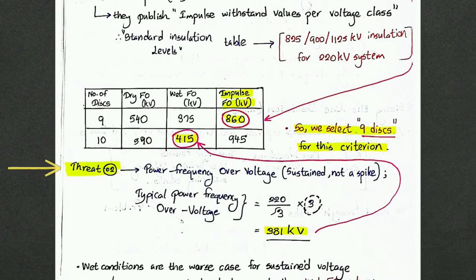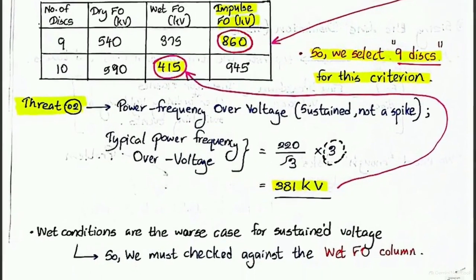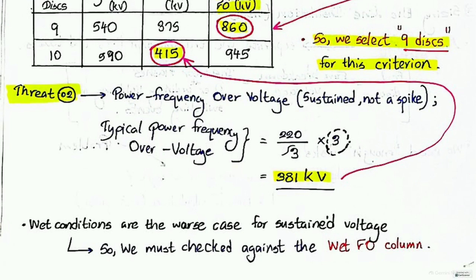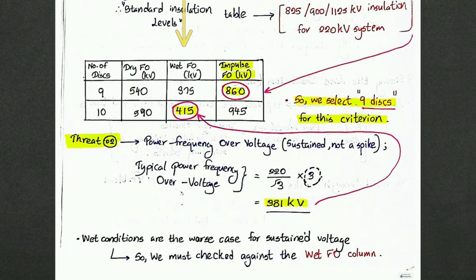But we also have to evaluate threat 2, sustained power frequency overvoltage. This is a continuous load rather than a fast spike, requiring a multiplier of 3, which results in a 381 kilovolt threat. This leads to a technical detail that is essential for real-world reliability. For sustained overvoltage, the standard is to check against the wet flashover column. Rain heavily degrades an insulator's performance, making wet conditions the necessary baseline for our calculation.